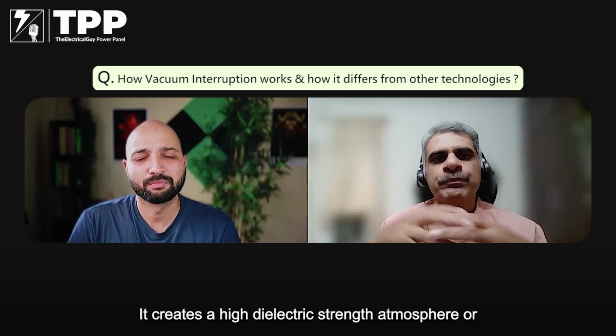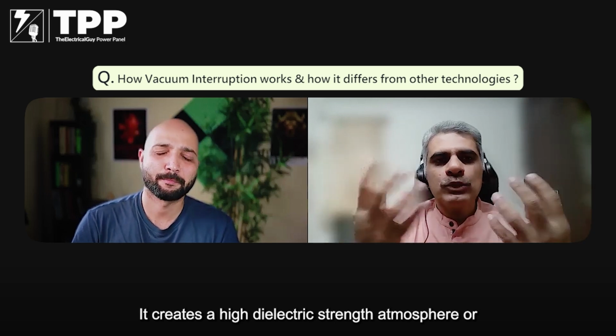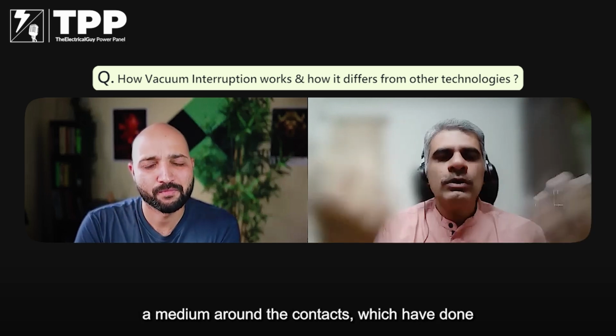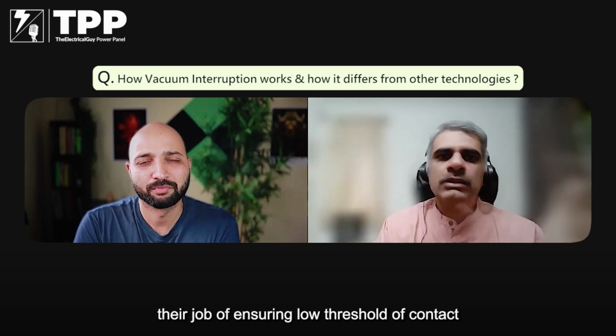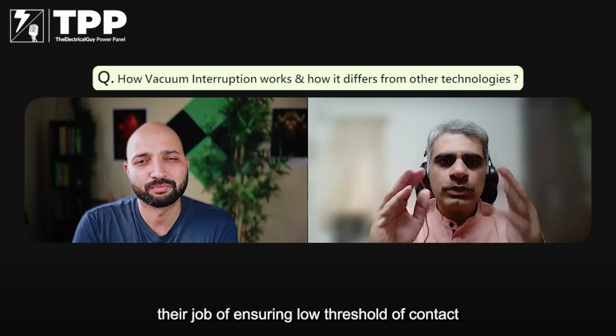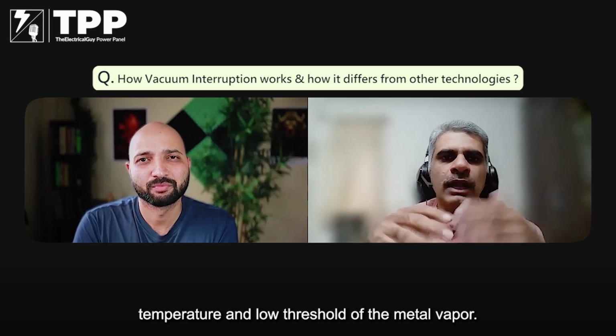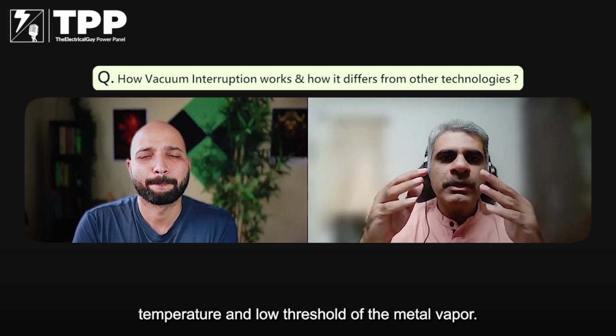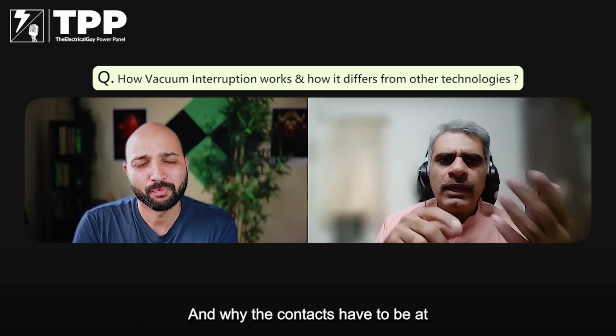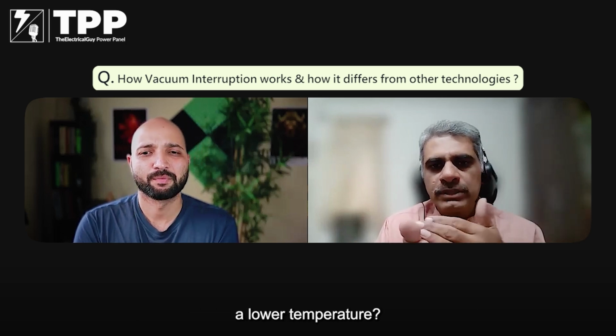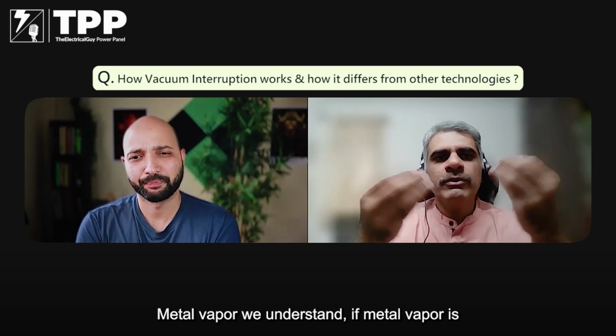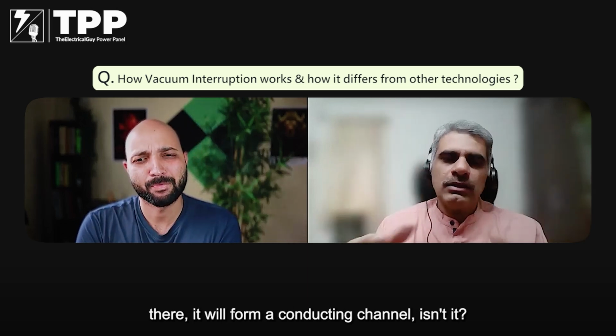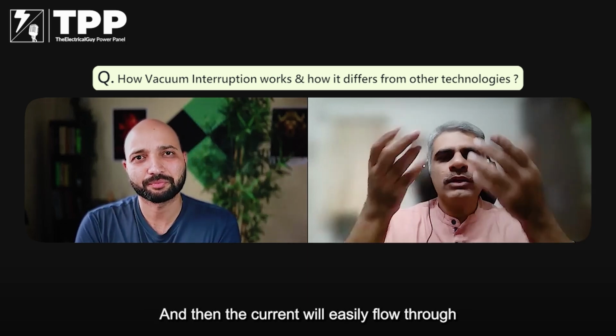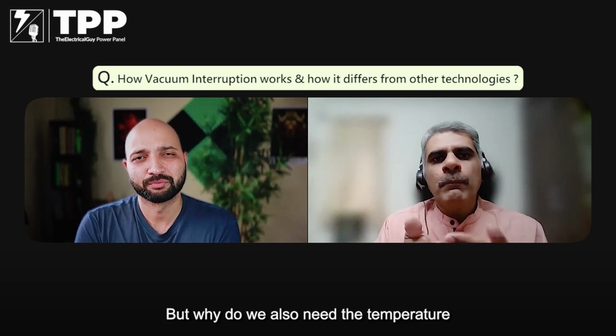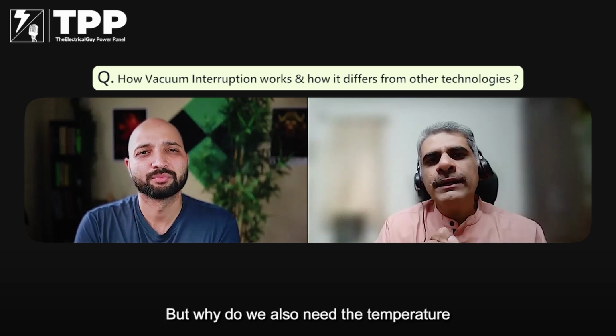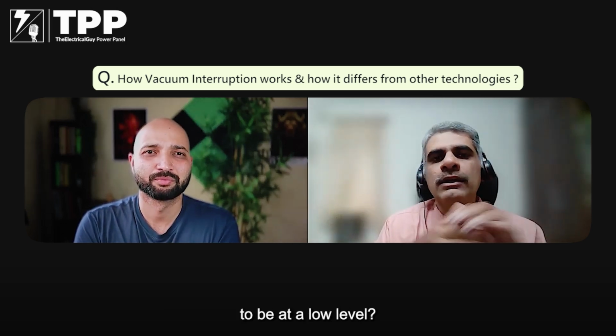It creates a high dielectric strength atmosphere or medium around the contacts, which have done their job of ensuring a low threshold of contact temperature and a low threshold of metal vapor. And why do the contacts have to be at a lower temperature? Metal vapor, we understand, if metal vapor is there, it will form a conducting channel, correct? And then the current will easily flow through this metal vapor. But why do we also need the temperature to be at a low level?